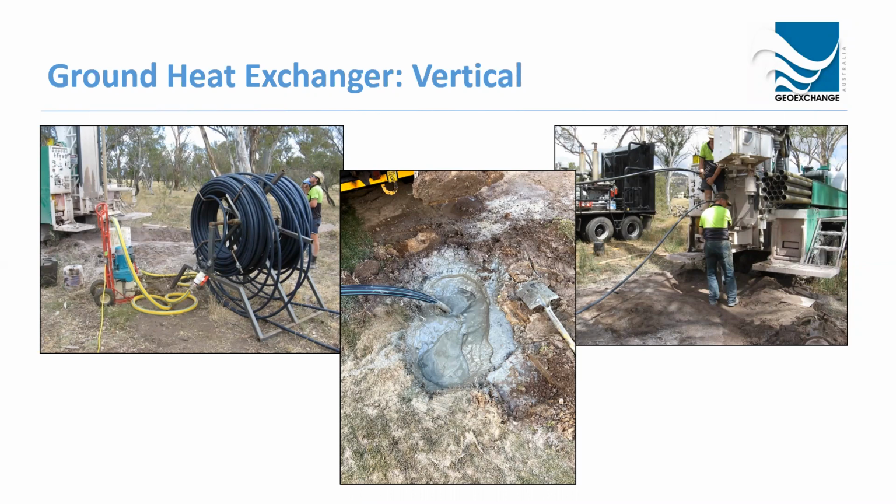When you've got a lot of water in the hole, the water will give you a lot of buoyancy. This becomes really hard to get over. It's the other reason why we fill the loop first with water before we put it down. You'll never push past the buoyancy point once you hit it. And you'll know when you hit it too. You'll think you're at the bottom, and then you check the markings on the pipe, and you're nowhere near it. So we do need to overcome that buoyancy. That's probably the hardest part, or the trickiest part, in terms of getting the loop down the hole.